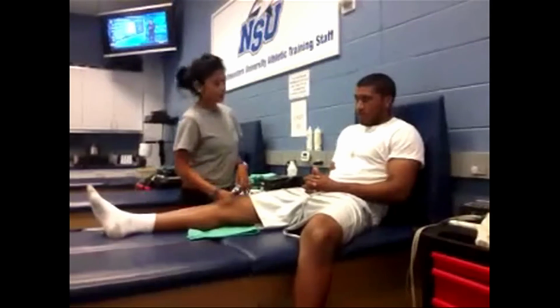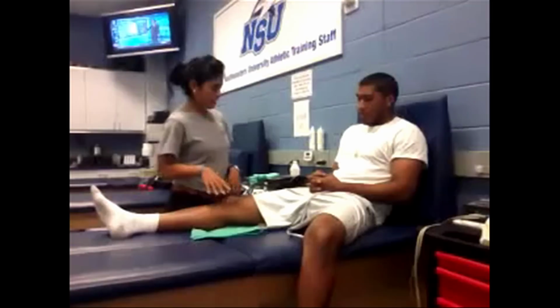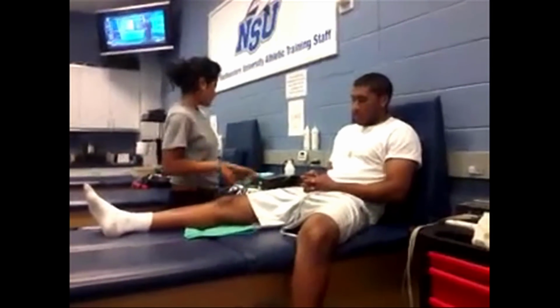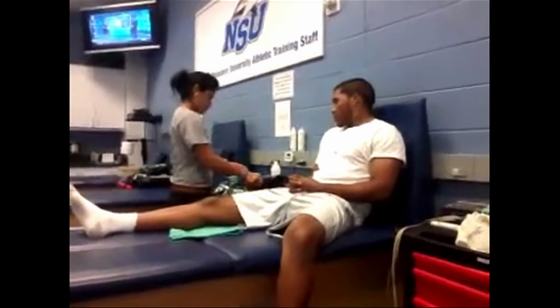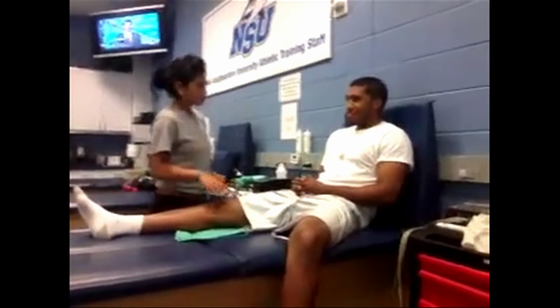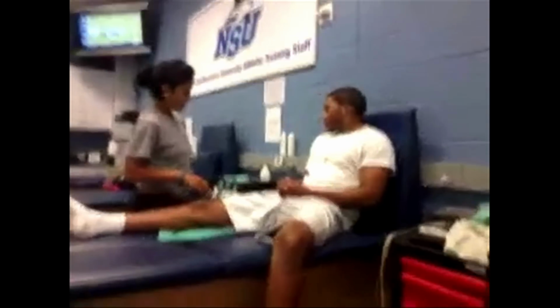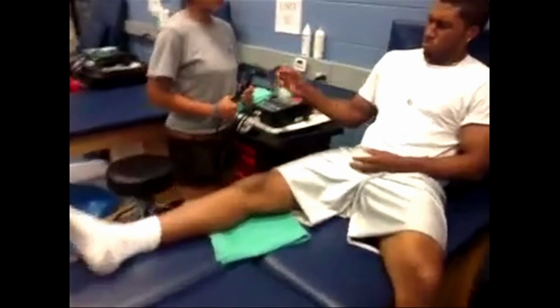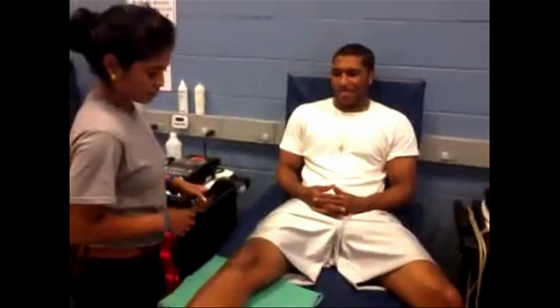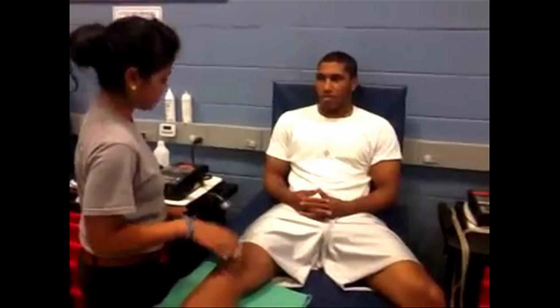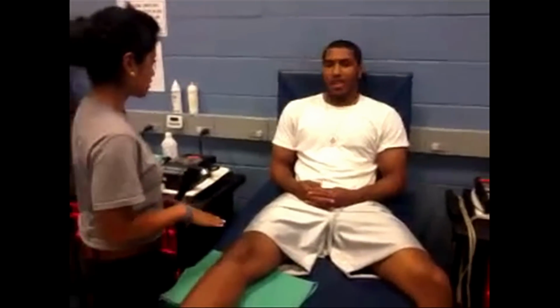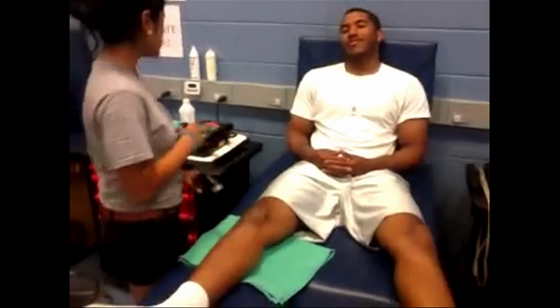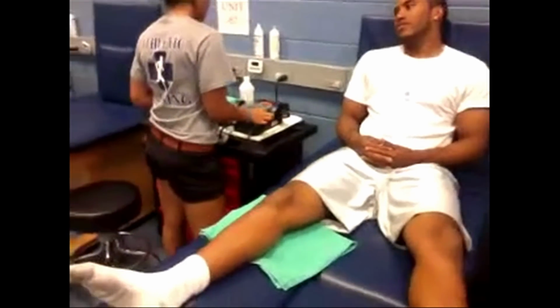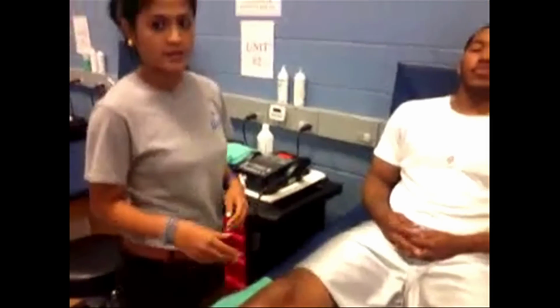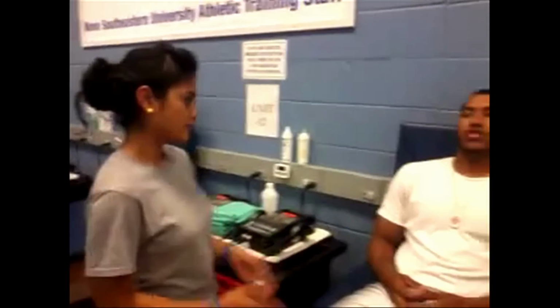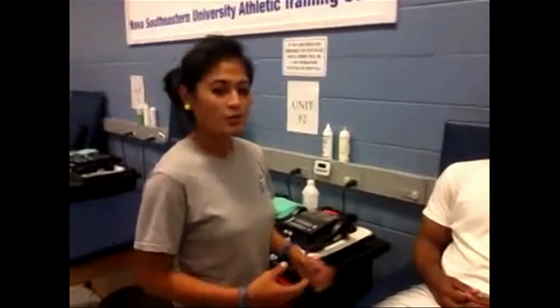So first off, I'm going to explain exactly what we're going to do. I'm going to be applying an ultrasound gel and a medication, and I'm going to be using this transducer head. You'll see here, this is called a transducer, and I'm going to be moving it in small circles, very slowly. And the parameters I'm going to be setting are... no, it's not hot right now. But while I'm doing it, you may feel some hot spots, and if you do, please tell me so I can immediately change treatment to non-treatment. The parameters I'm going to be setting are 3 megahertz, continuous, so that there is a thermal effect with the ultrasound, and about 0.5.